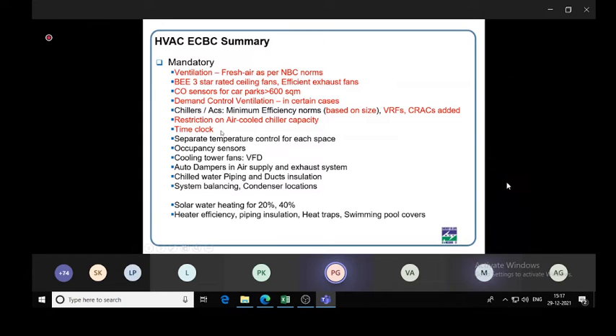Time clocks, again for more than 20,000 square meter buildings, time clock should be there. Separate temperature control for each space. Occupancy sensors, again for certain spaces. VFD controls for the cooling tower fans. Minimum level of insulation for the pumping and piping and chilled water pipes and ducts. And solar water heating, minimum 20% of the overall requirement should be there for basic compliance. And if it is more than 20,000 square meters, then 40% of the hot water requirement should be from solar.